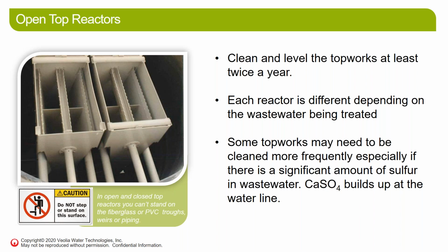Jack, I just want to butt in here and say, be careful when you're cleaning these. Typically, it's pretty easy to clean them with just a hose and or a brush or a broom. Most of the time, you don't need to power wash them. Correct, because most of the stuff is all fiberglass, so high pressure is going to damage the fiberglass if you try to use a typical power washer on it.